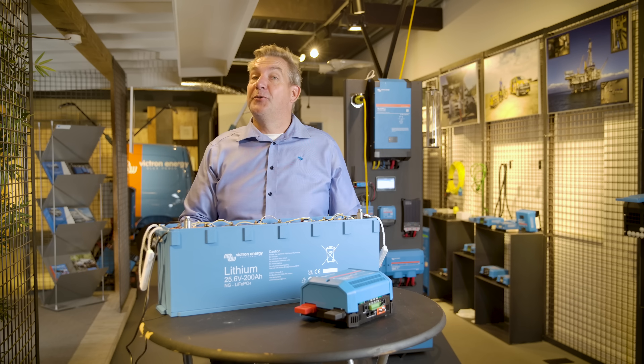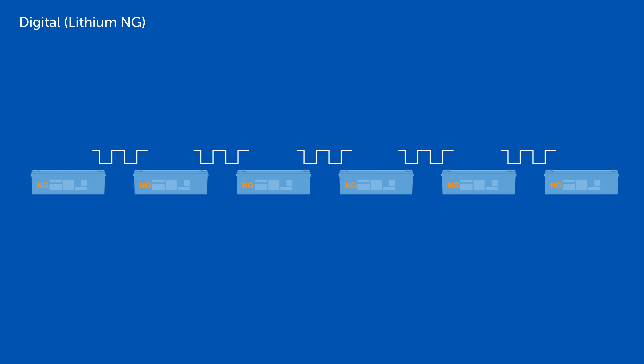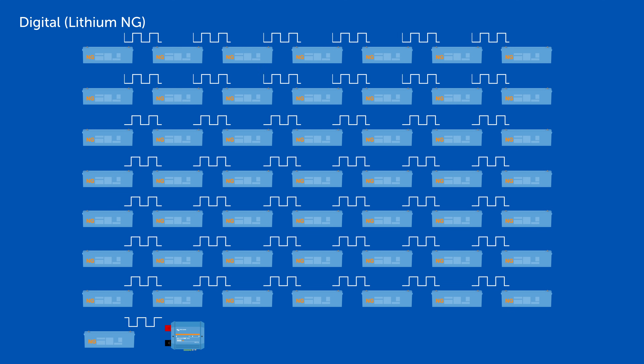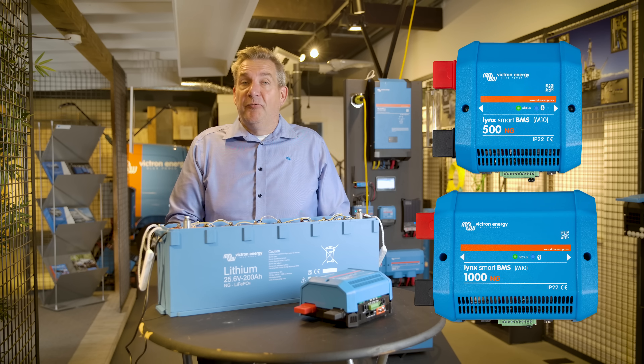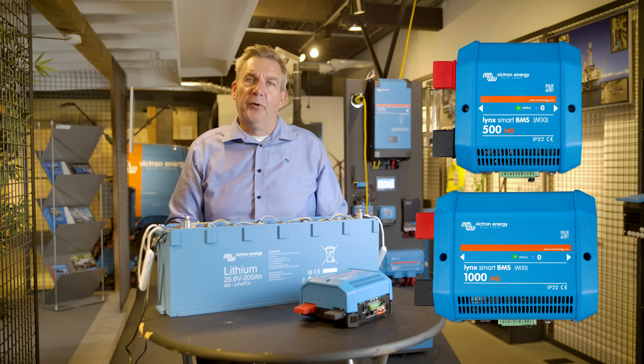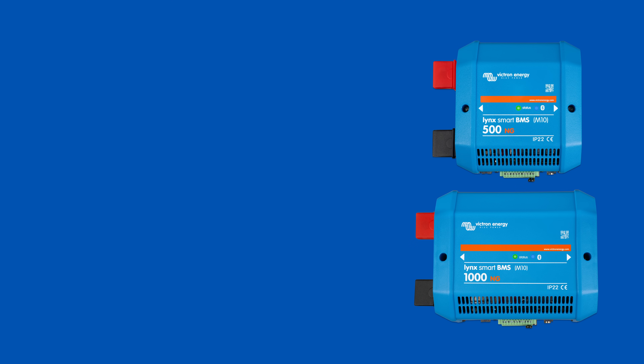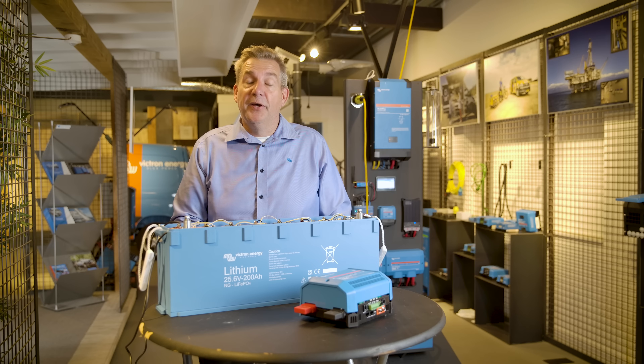The digital communication also enables us to make larger systems. With analog signal transmission, the signal gets weaker with each battery connected, limiting the number of batteries you can use. With digital communication, that's not the case — you can connect up to 50 batteries on one single BMS. There are two Lynx BMS options available: a 500 amp and a 1000 amp, each supporting up to 50 batteries. That means you can go up to 384 kilowatt hours. If that's not enough, you can also parallel the BMS units for extra power or added redundancy.